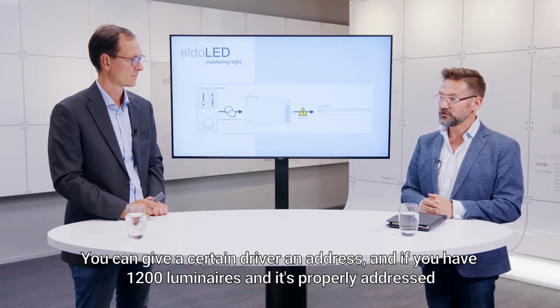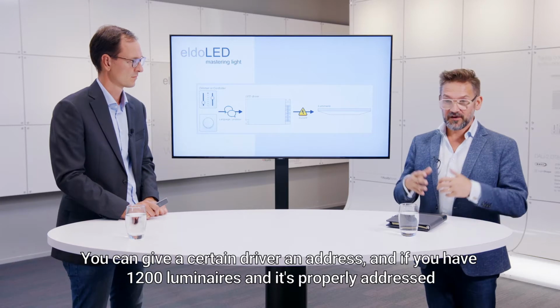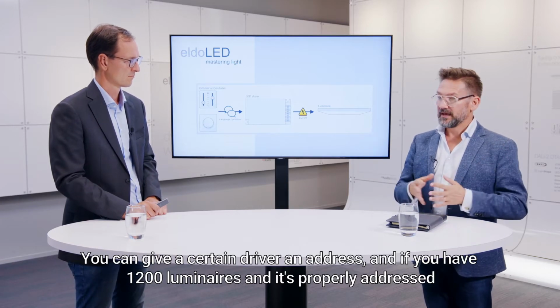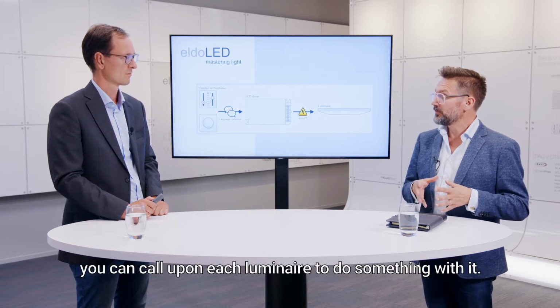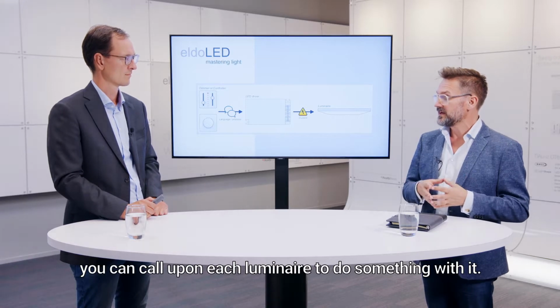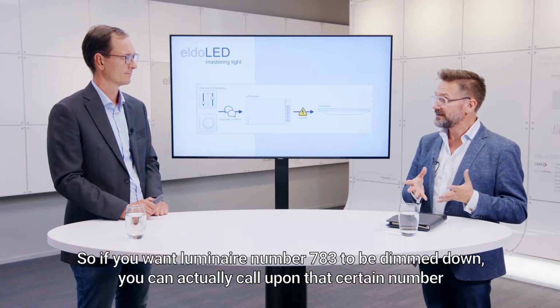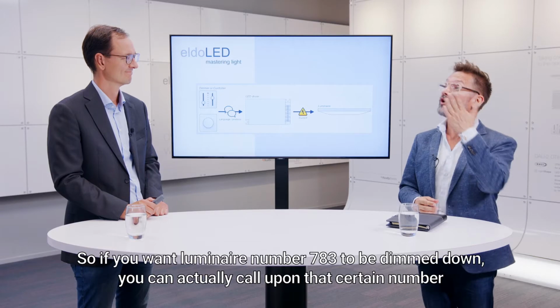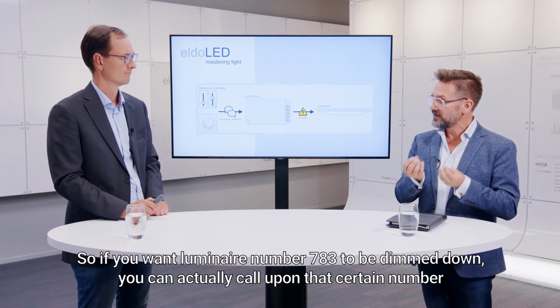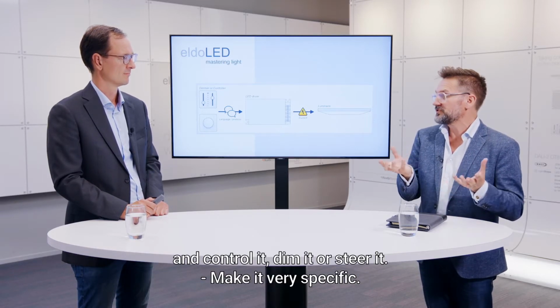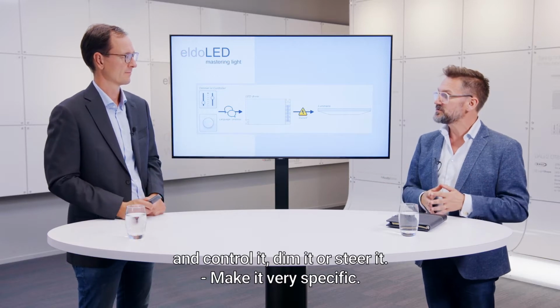You can give a certain driver an address, and if you have 1200 luminaires, and it's properly addressed, you can call upon each luminaire to do something with it. So if you want luminaire number 783 to be dimmed down, you can actually call upon that certain number and, well, control it, dim it or steer it in the way that you make it very specific.